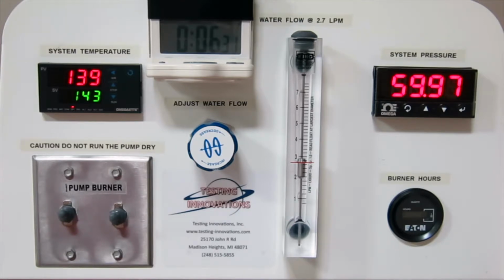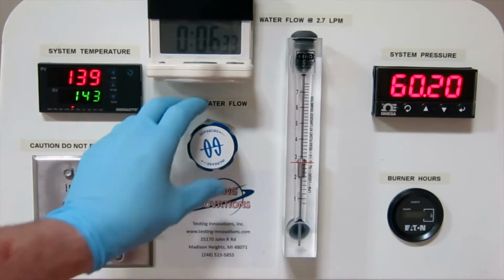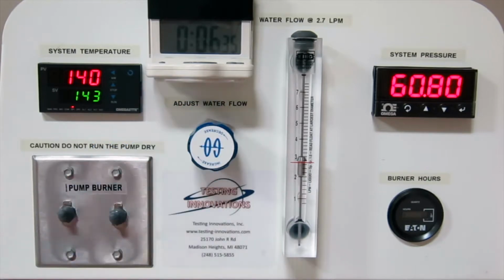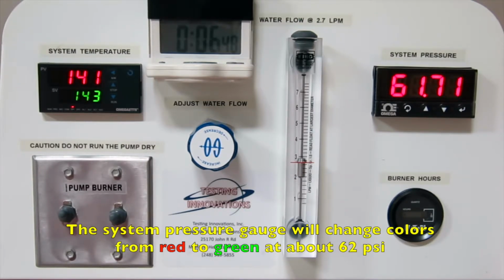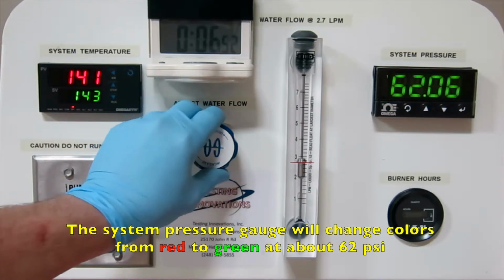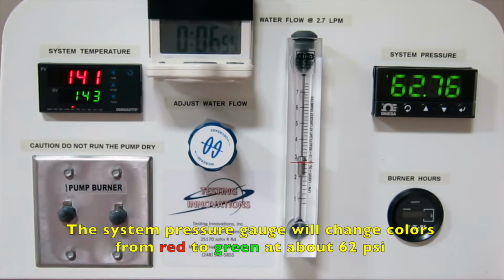At about 7 minutes into the machine warm-up, your adjustments will slow down to approximately every 30 to 60 seconds. At this point, try keeping the largest diameter of the float just a hair below the 2.7 liters per minute target line on the flow meter. You will also notice that the system pressure gauge will change colors from red to green at about 62 psi to let the operator know that he or she is very close to the target values.